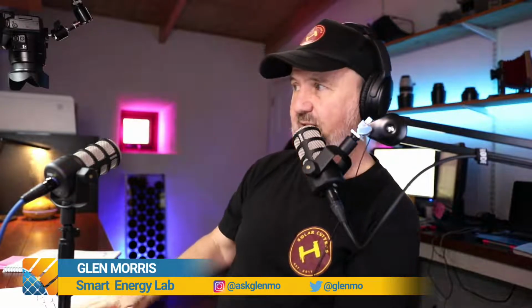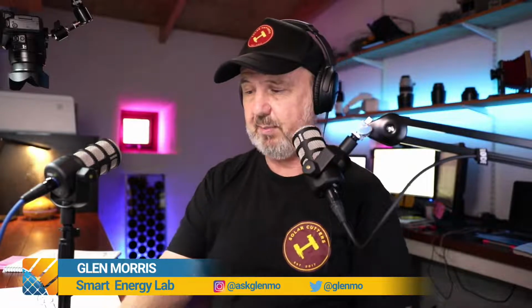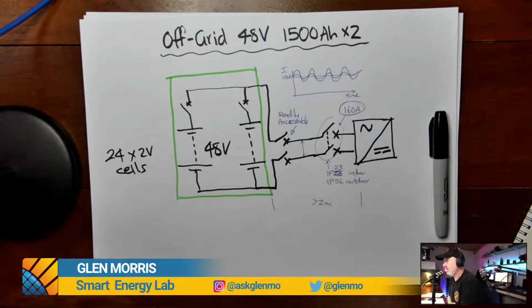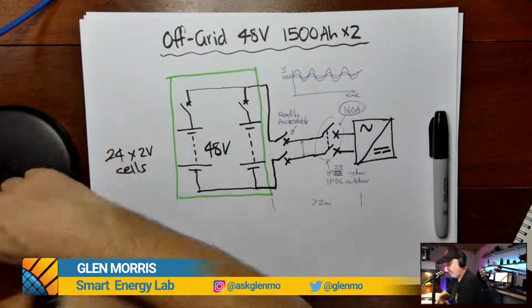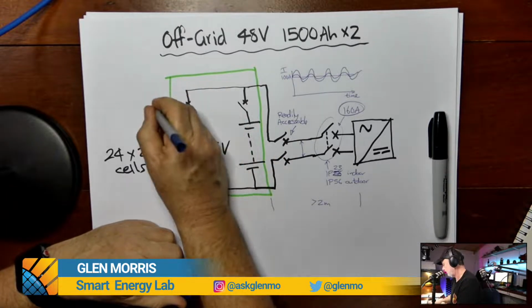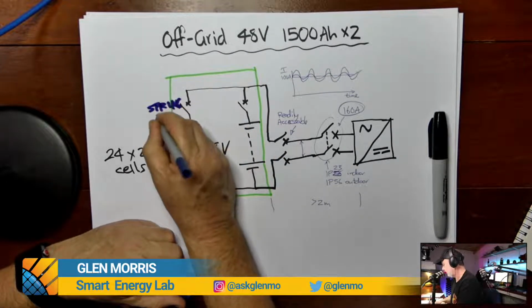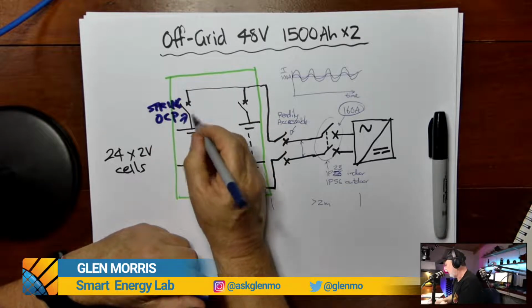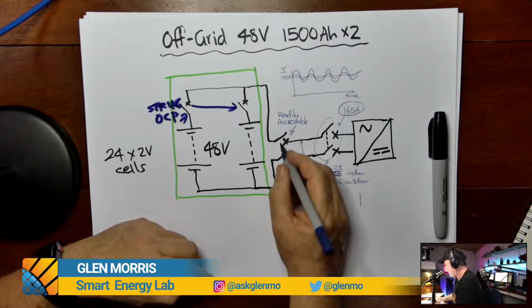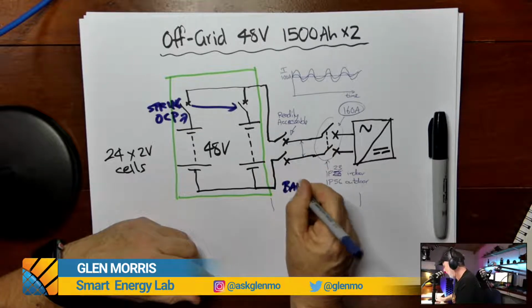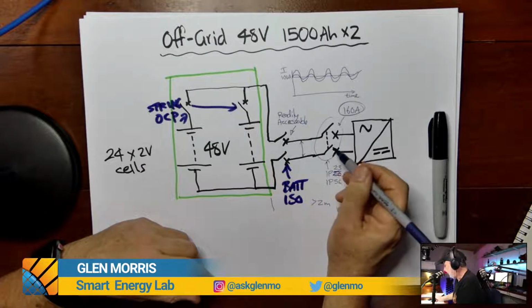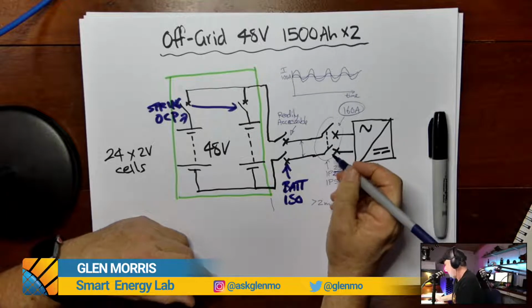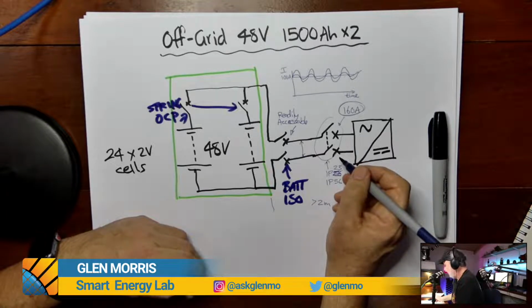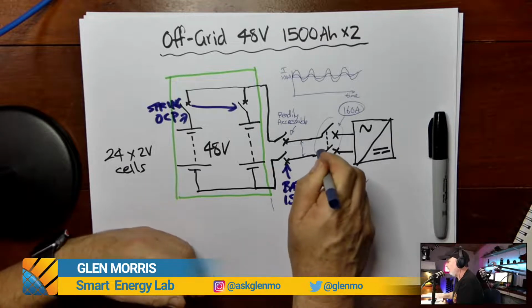Okay, so we've designed a system. I'll just cut back to it so you can see it. It's a 48 volt lead acid system with 1500 amp hour sealed cells. We've put in the string overcurrent protection, so this is our string overcurrent protection devices here and here, and this is our main battery isolator. I'll just call it a battery ISO here. Now this other one is in just for the purpose of distance. If the PCE is more than 2 meters from the battery system, then that secondary one's required.